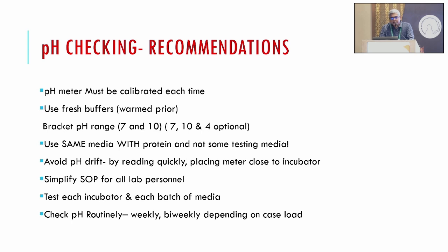The bracketed range of pH buffer should be according to the pH. For example, we are looking for a pH of 7.2 to 7.4, so we should be using 7 and 10 ideally, or if possible 7, 10 and 4 also. Always use the same media with protein, not without protein, and not some other media. You can use the media from the previous batch if it's not too old or if the color change is not too much. Always avoid pH drift by reading quickly or placing the meter close to the incubator.